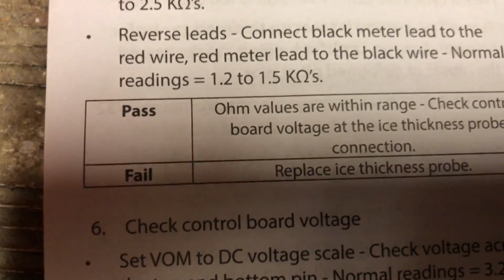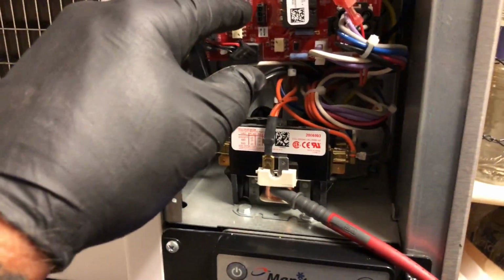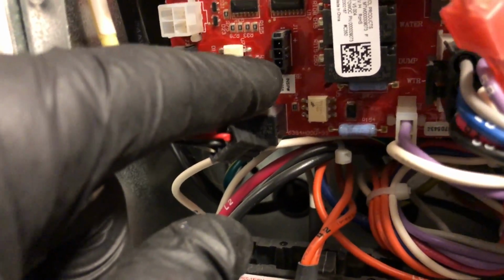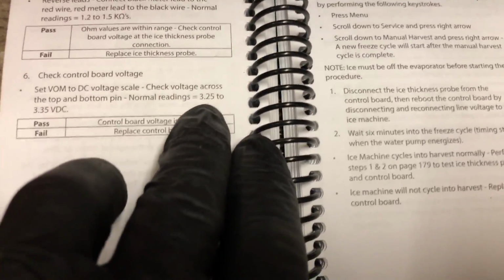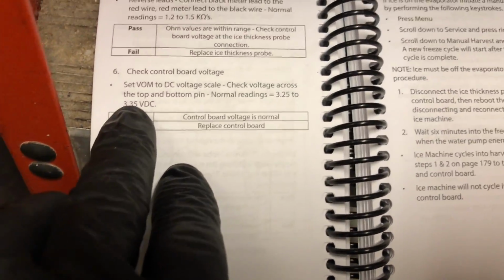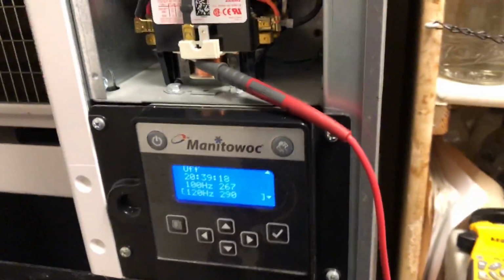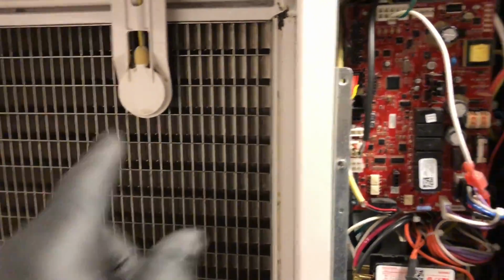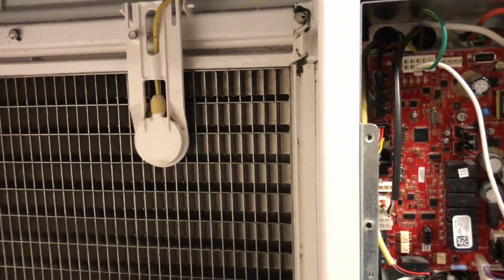1.2 to 1.5 is a pass. The last thing you check when the unit's running is from this top pin to the bottom pin, DC volts, and you're going to look for 3.2 to 3.3 DC volts while it's running. That's your check for your board and your ice thickness probe on the Indigo.